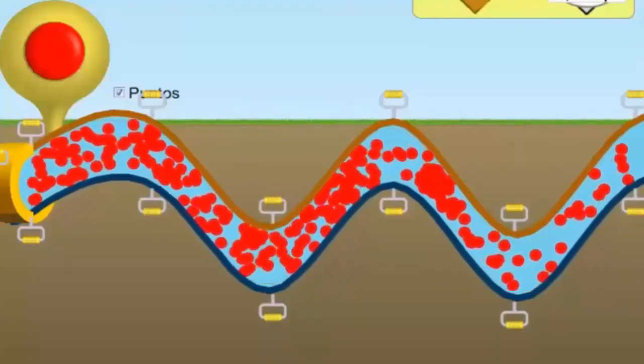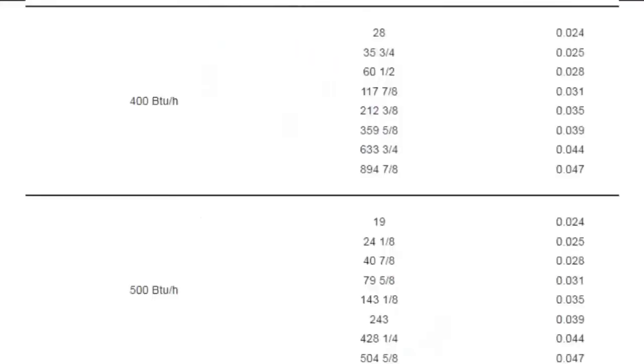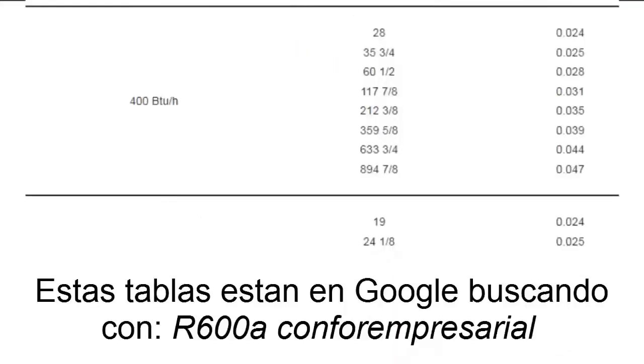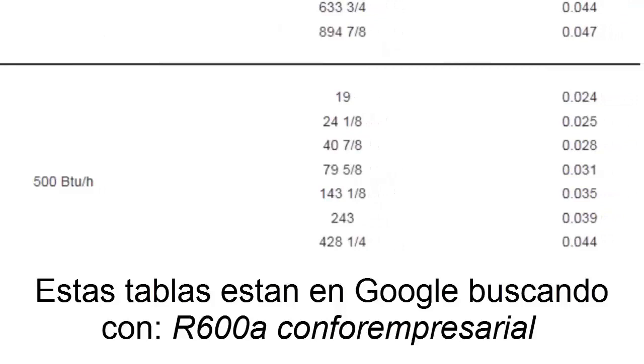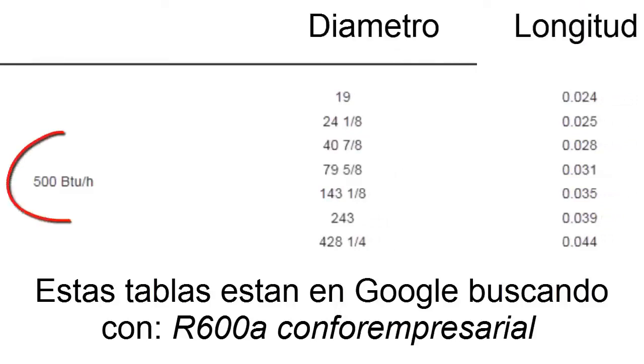On the screen we have a table that allows us to select the diameter and length of the capillary that will work with R600a. To make the selection, we must know an approximate cooling capacity of the compressor.